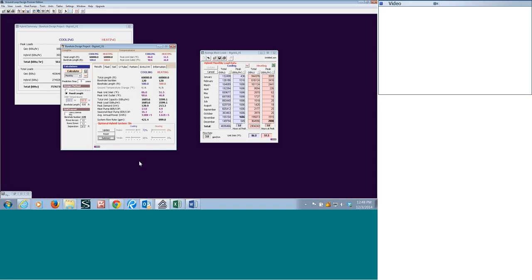Well, what they were doing, they were overriding this, and they were banging this thing from cooling to heating. I think there were 8 of these 30-ton water-to-water units, and they were hitting them so hard they were eating compressors. They were rotating the heat pumps, but still they were probably going through these nominal 15-ton compressors, oh gosh, as many as 5 or 6 a year. And of course, they had 2 15-ton compressors in each heat pump. So that was pretty expensive, plus there was a lot of downtime.